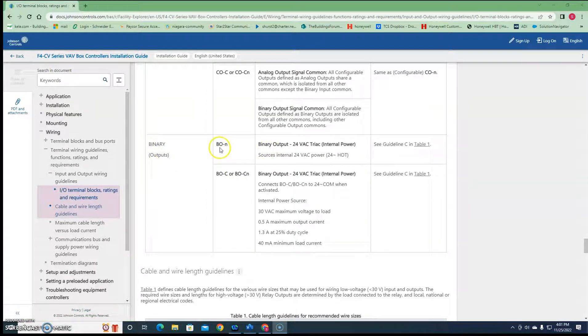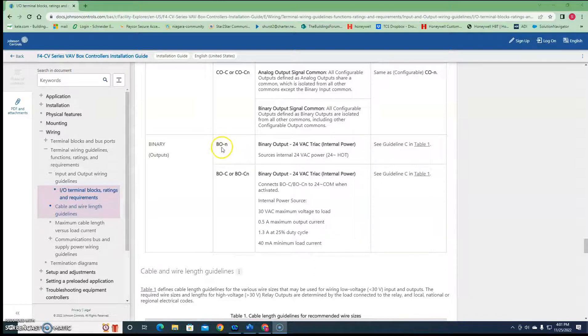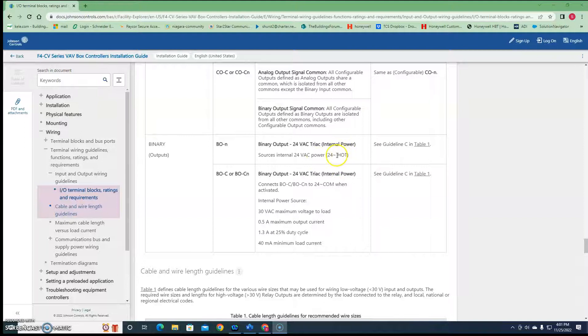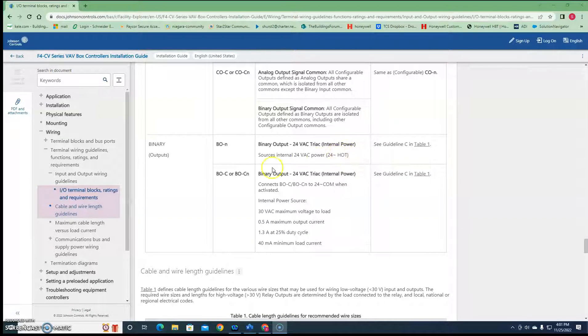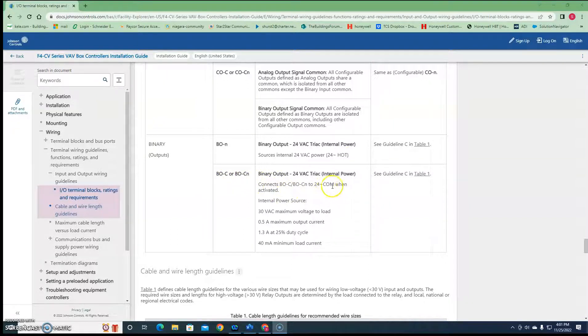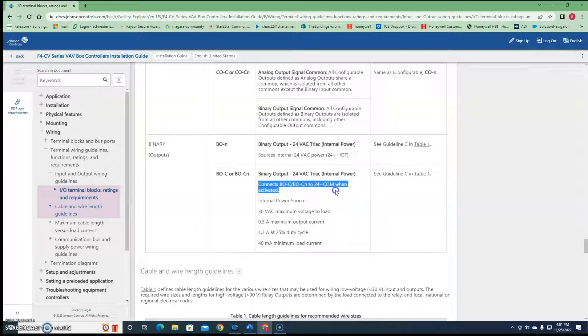So BO and then the number, BO1, BO2, BO3, is a binary output 24 volt hot. So it stays hot all the time. Binary output common or common and the number switches on when activated right here.